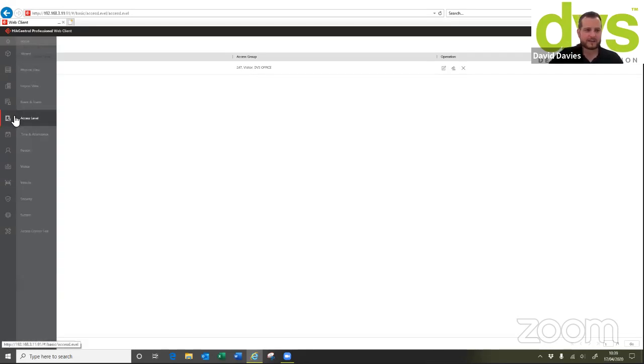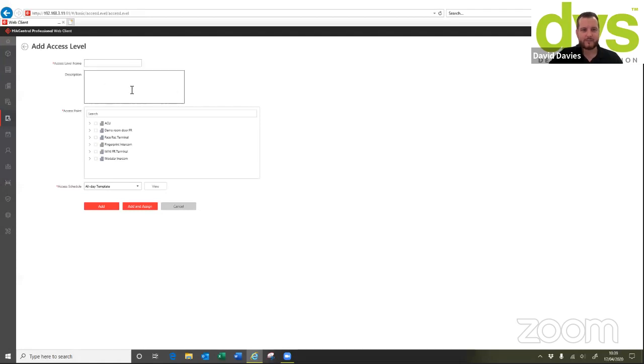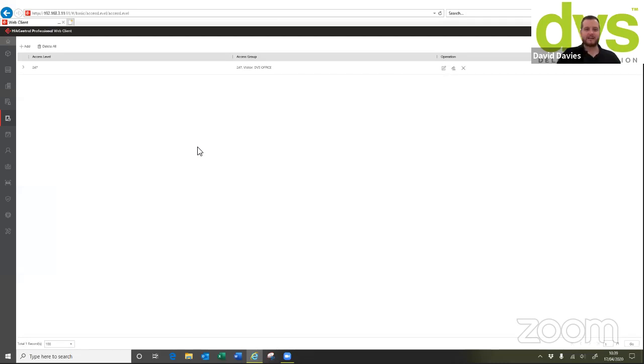But again, the access level is as simple as adding one in, building it up that's appropriate to the site. So you've got default 24/7, but you could have 9 to 5, weekend only, whatever that is. You give it an access name, tell it what it is. So 9 to 5, not 9 to 15, there's no such thing. And then you select the appropriate devices, select the schedule that applies to that, click on add, and then that's an access level within the system. So again, that's really down to how the site requires you to build these access control hours up, no different to any access control system.